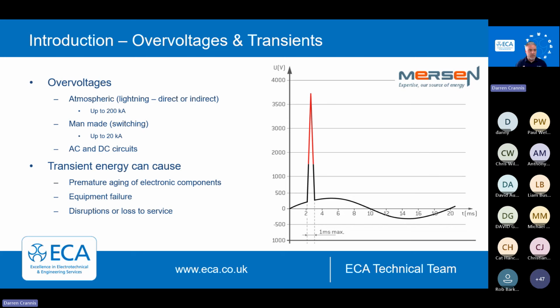Fortunately, in the UK, we're not that lucky. Typically values of about 100 kA. So that's a lot less. And you might see Type 1 SPDs that have values of 25 kA. And you wonder, why is it 25 when lightning's 100? Well, that lightning being 100, when it hits the lightning protection system, 50% of that's going to go into the atmosphere. 50% of that's going to travel down the conductor. 50% of that will go to Earth directly. The other 50% will end up in your electrical installation. And that's where that 25 kA comes from, a Type 1 SPD, which is traditionally a lot bigger. It's got a lot more energy to take, and we'll come on to that later on.